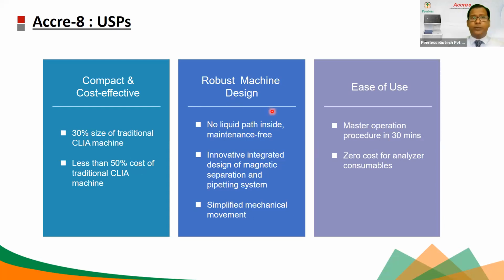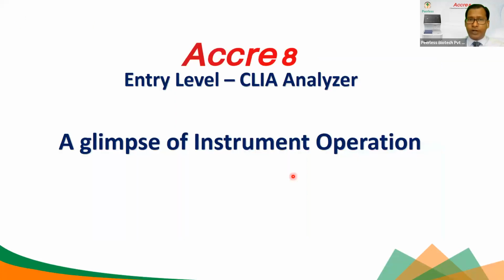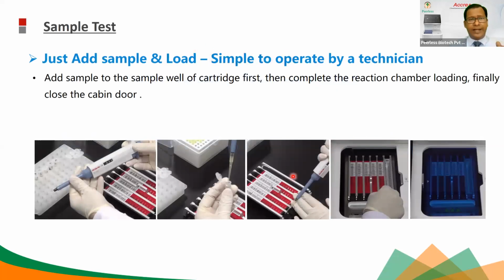And it has a robust instrument design because there is no liquid path, with an innovative and integrated design for the magnetic separation and pipetting system. The mechanical movement is very simplified, so the trouble with the machine is lesser. And it is very easy to use, so it can be used as a point of care analyzer. Now I'll go into more details of instrument operation, how to do the operation a little bit. I'll not touch much because you may not need to know it in detail, but to give you an idea, it's a very simple idea. Just add the sample and load. Very simple to operate by a technician.